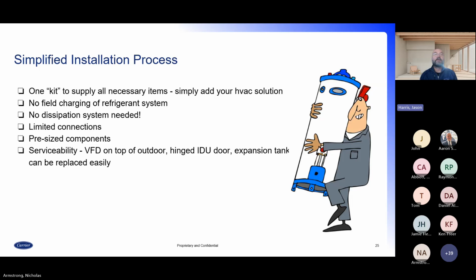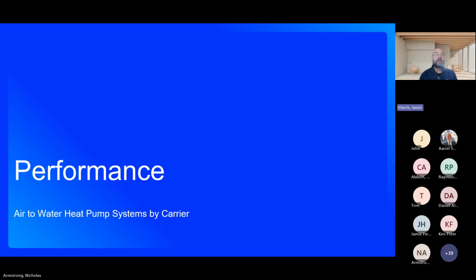So you have one kit with everything you need. It is a monoblock design, so you don't need to worry about refrigerant charging. You really don't even have to hook up any gauges to the unit. All the pressures and temperatures can be read through the outdoor or the indoor unit. It's easily serviced. You can remove the top of the outdoor unit to see all the boards. On the indoor unit, you can access the elements and the expansion tank. Everything is easy to access, and your amount of connections is limited. It's water connections between the indoor unit and outdoor unit. Next slide.